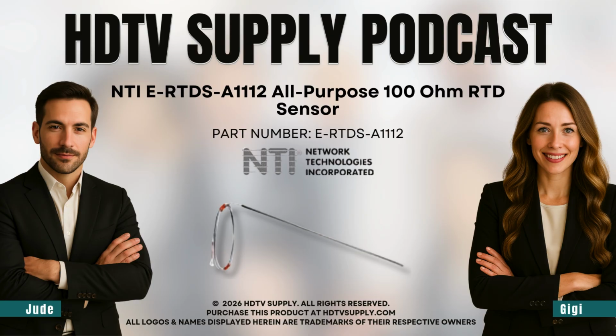And that 316 grade is important. It's not just any steel. It's built for corrosive environments, with salts or chlorides. That's part of its all-purpose claim. Okay, but I saw something interesting about the wiring. The probe can take the heat, but the 40-inch lead cable is only rated up to 482 degrees Fahrenheit. So why the huge difference? That's a great catch. It's a classic engineering trade-off. The sensor tip, the part doing the work, is in the extreme environment. Right. But the cable and all the electronics it connects to are assumed to be a safe distance away. High-temp insulation for wiring gets very expensive, very fast. So it's a cost and design compromise.